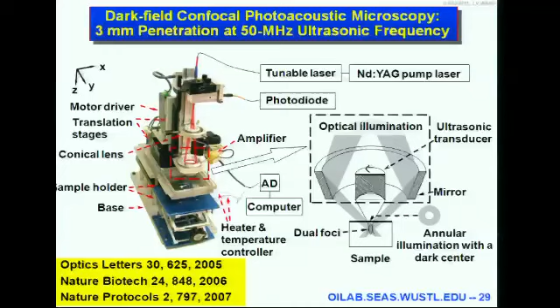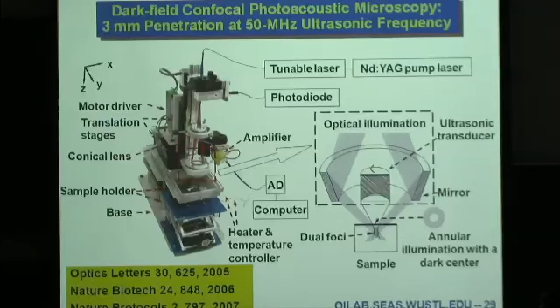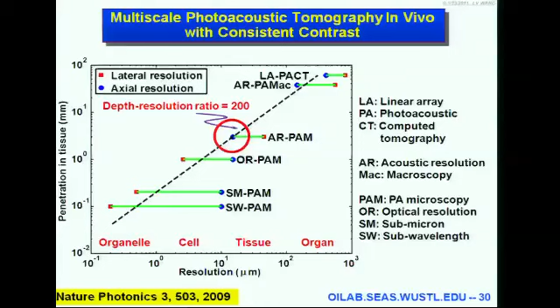This is the first 3D photoacoustic microscope. Starting from a laser, route the laser beam through optical fiber. The solid beam comes out of the fiber. We convert this solid beam into a hollow beam through this conical lens. This hollow beam is refocused down through this element, shown in this close-up, onto the tissue. On the tissue surface, we have this donut beam. So the core is dark just to minimize the surface interference. This ultrasound transducer is confocal with our light illumination just to maximize the signal-to-noise ratio. This scanning head is raster scanned in this water tray. Through the membrane window, we transport light and sound. So the tissue we want to image is placed below the membrane window. This system works around this spot. A few millimeters penetration, tens of microns in resolution.